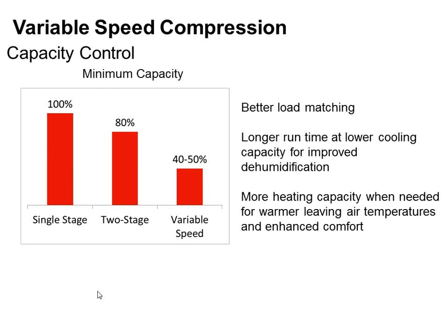The variable speed capacity is what kind of makes this all work. So a normal unit, it's either running at 100% or 0%, right? A normal condensing unit or heat pump, it's either on or it's off. If I were to buy a 2-stage air conditioner or heat pump, in your mind, it'd probably go 0, 50, and 100% capacity. Oh, if I only run 1 stage, it's probably 50%. That's not really the way it works. It's really 0, 80, and 100%. When I shut off 2nd stage and run 1 stage by itself, for most of these units, it's between 70 and 80% capacity, not the 50% that you probably imagined it to be, or that I imagined it to be anyway. So you're only staging down that much. Yes, it helps out having 2-stage equipment. It's way better than 1-stage equipment, but it doesn't ramp down all that much.